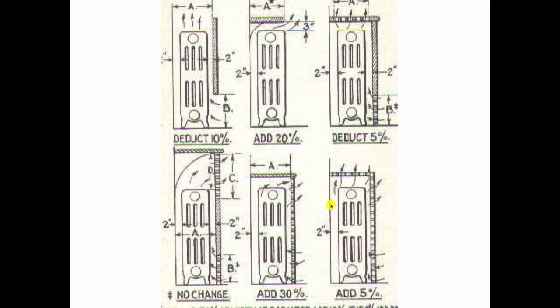So painted silver cuts 20%. Use this sort of enclosure, cuts an additional 30%. That's how they dealt with the radiators that were oversized as a result of the Spanish influenza. And notice while we're on this slide that every radiator is placed two inches away from the wall. That was always the ideal spacing.